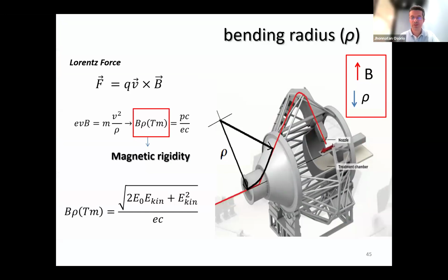Then, a few words about physics. Why so big? Why are the carbon ion centers and the proton centers so big? Basically, because we can control the beam only using the Lorentz force. So we bend the beam in one direction and another purely with the Lorentz force. We accelerate the beam with the RF cavities, that is, with the electric field. So here, if you do a little bit of really simple gymnastics, you end up with the fact that the energy you want to give to your particle is strongly correlated to the magnetic field available in your system, and rho, the bending radius, is proportional to the energy.